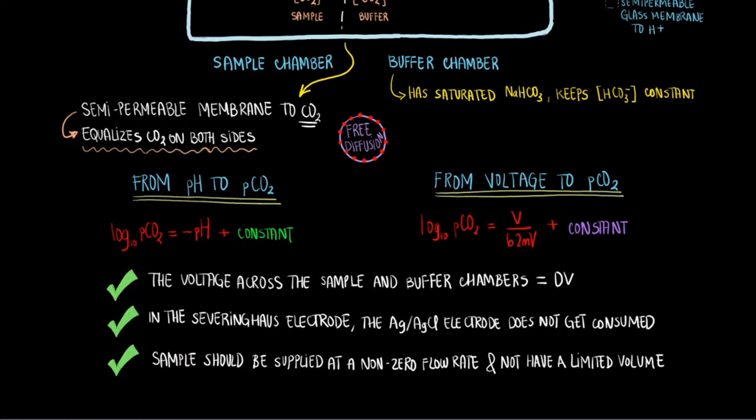Third, your sample should ideally not have a limited volume or a fixed finite volume. It should flow through the chamber with a non-zero flow rate. This is particularly important to ensure that enough CO2 from the sample is provided to the chamber. Otherwise, the sample CO2 will get comparatively diluted by the buffer solution CO2 concentration. We hope that this was helpful and you were able to learn a bit more about the Severinghaus PCO2 electrode.